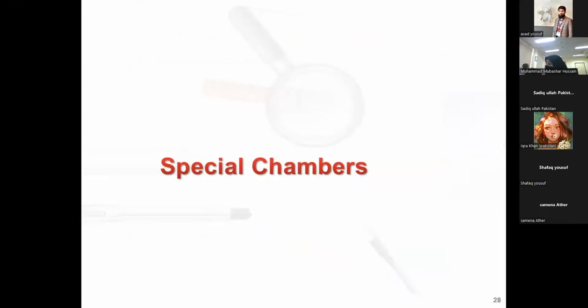All these Farmer chambers and Farmer type ion chambers have a prerequisite that they can be used only in a uniform radiation beam, where the dose gradient is almost negligible. That is why when we are using a Farmer type chamber for our dosimetry, we require a broad radiation field, say a reference field size of 10 by 10 centimeter square. The Farmer type chamber is placed in the center of the radiation beam, where the beam is uniform. This Farmer type chamber cannot give us readings accurately in the penumbra region, where the dose gradient is high.